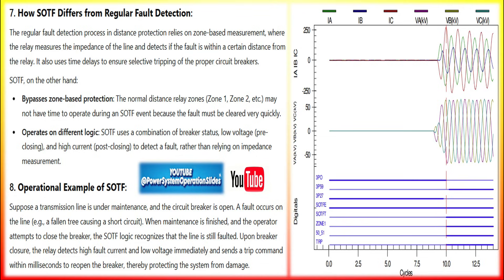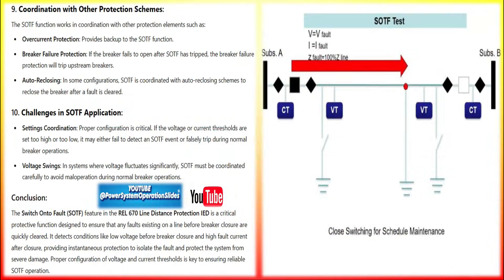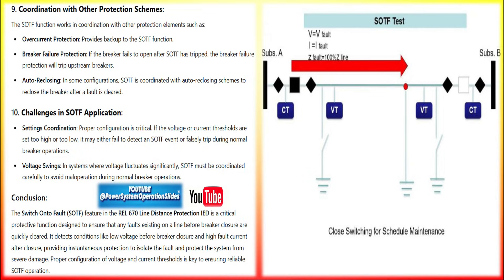The SOTF function typically activates under these conditions: first, breaker closing onto a fault — when the breaker closes onto a fault, there will be a sudden increase in fault current. Second, detection of low pre-fault voltage — before the breaker closes, the voltage across the line is usually low, near zero if there is a fault. The relay monitors the line voltage and senses that there is no healthy voltage present before closing. Third, high fault current on closing — as soon as the breaker closes, if the current rises sharply, indicative of a fault, the SOTF function is triggered.